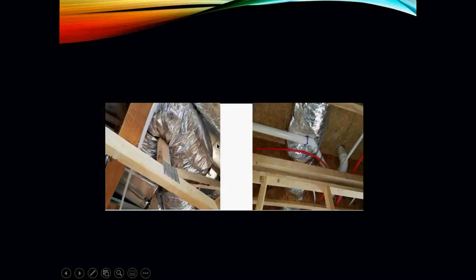Another issue that you could run into is very tight bends. I mean, look at this guy right here. That is a greatly reduced piece of flexible duct. That's not going to work so well. It looks like that's probably a return. Air is getting sucked back into the air handler, and if we're not getting the proper amount of return air, you're not going to get the proper amount of supply air. They go hand in hand.